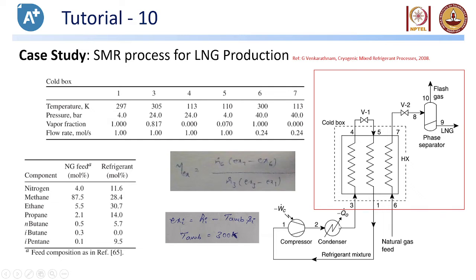If you want me to explain the process requirements: we want to cool this. However, the refrigerant is not sufficient to provide the cooling unless it is cooled and then expanded. For that reason we cool it to temperatures of around 113 Kelvin, and then expand it from 24 bar to 4 bar to get the refrigeration effect.